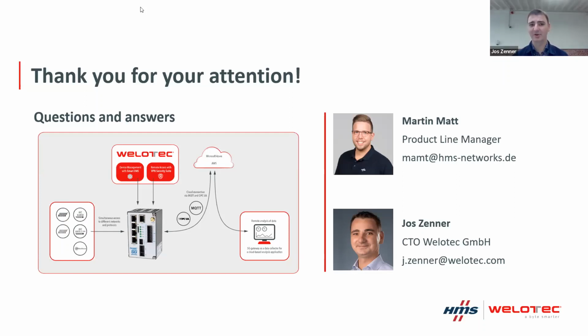Well, Modbus is a non-encrypted protocol. If we are using VPN Security Suite, we put end-to-end encryption over it. So you have encryption, and you also have data integrity in terms of the VPN, but you don't have data integrity of the protocol itself. Usually you don't use Modbus between the gateway and the SCADA system; usually you would use 104 with the security extension, or MQTT with the security extension, or with the VPN, and then you have some additional security. If you really want security by default, you need a protocol that meets those requirements. Modbus is easy and great to use, but it's probably not the best one for northbound connectivity.